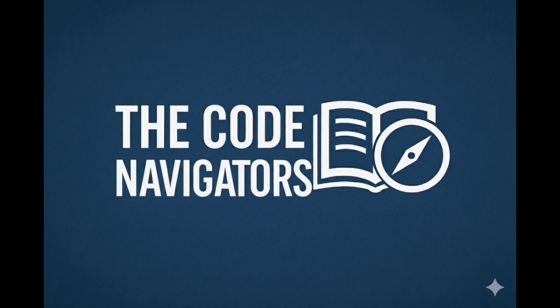What about automatic fire extinguishing system? Sounds similar to sprinkler system. It's a broader category than just sprinklers. An automatic fire extinguishing system refers to any system that's designed to automatically detect a fire and discharge an approved extinguishing agent to suppress or put out the fire. So the agent doesn't have to be water. Exactly. It could be a clean agent gas, like in the server room. It could be chemical foam, like for flammable liquid hazards. It could be dry chemical powder, or it could be water, including sprinklers or water mist. It's a general category for automated extinguishing systems.